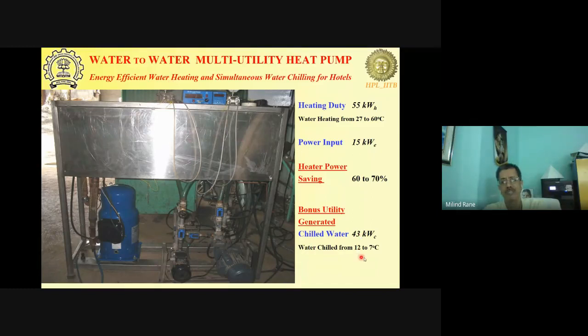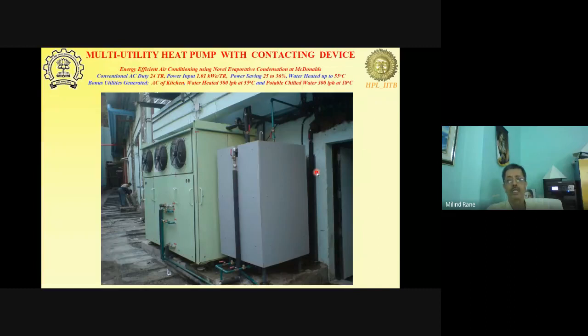So on one side, we are chilling water from 12 to 7, similar to what a conventional air conditioner chiller would be doing. And on the other side, the heat from the evaporator plus the compressor power of 15 kilowatts is delivered as heating utility. Now here you'll note that around 3 kilowatt, it should be 58, but we are recovering only this because there will be some heat losses and things like that from the uninsulated pumping and other things from the compressors and all. So even with this, 55 kilowatt of heating with 15 kilowatt of input power is a very attractive deal. And to top it off, now we are able to get 43 kilowatts of chilled water. This we developed through Ministry of Textile funding. And we are deployed in Club Mahindra, Goa, and many other automotive industries also. This was the thing which I had discussed in detail, a 24-ton system with 2 compressors.